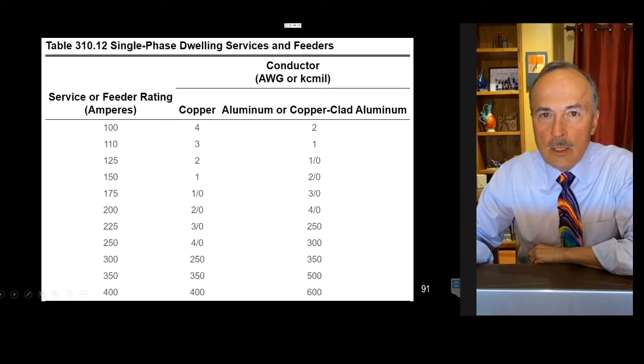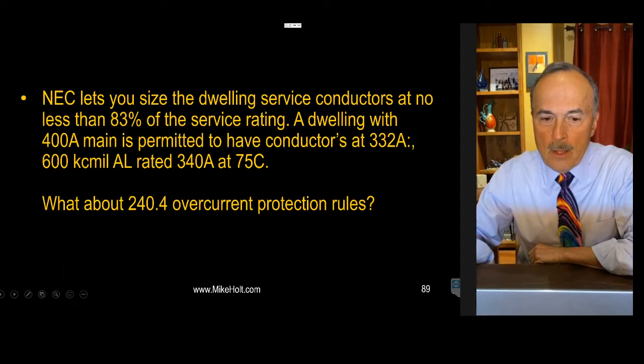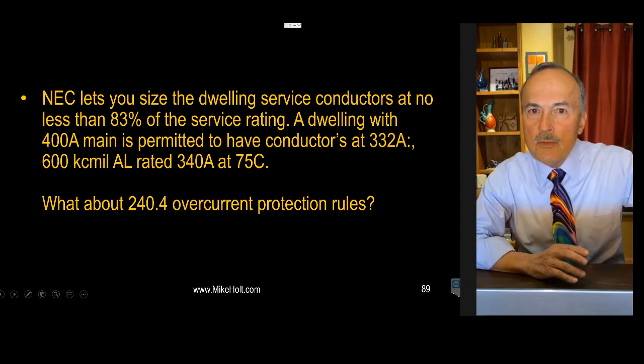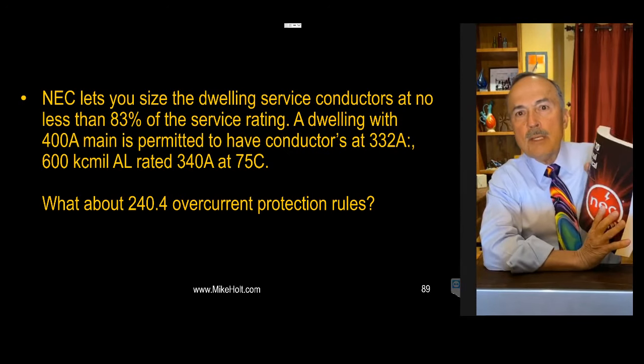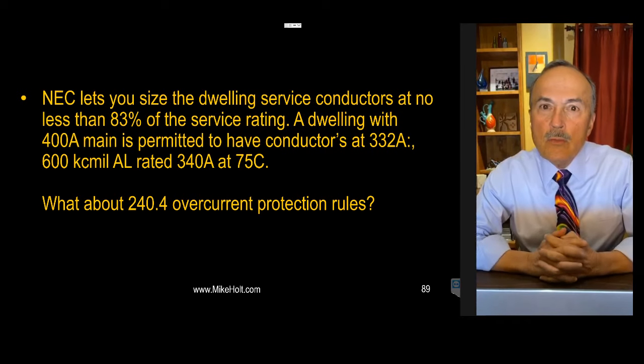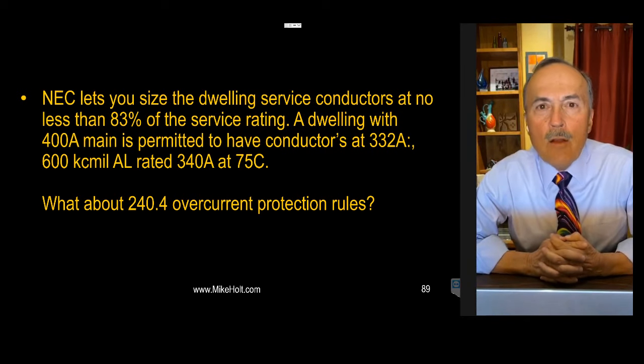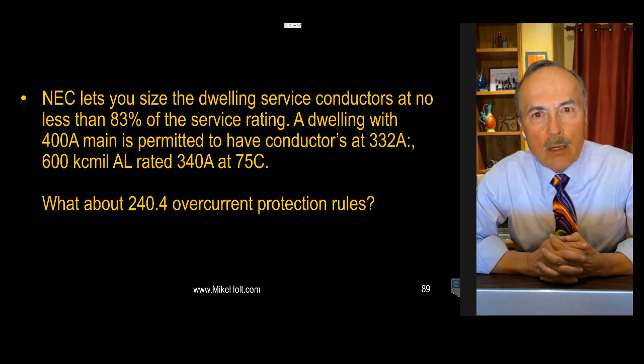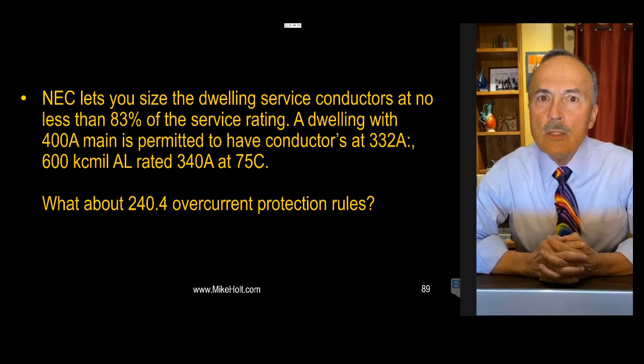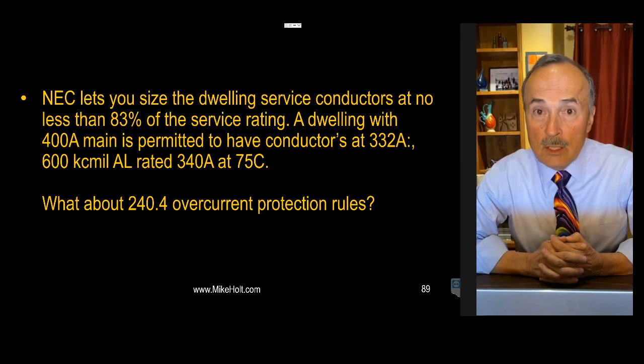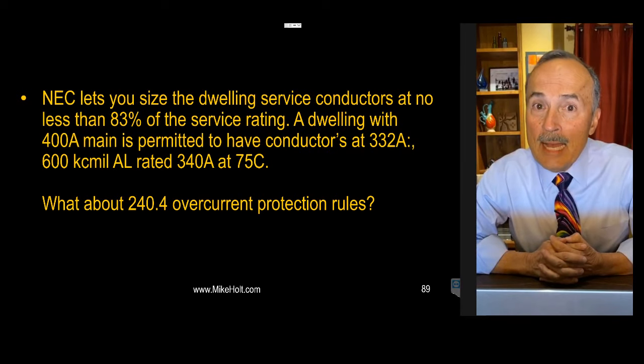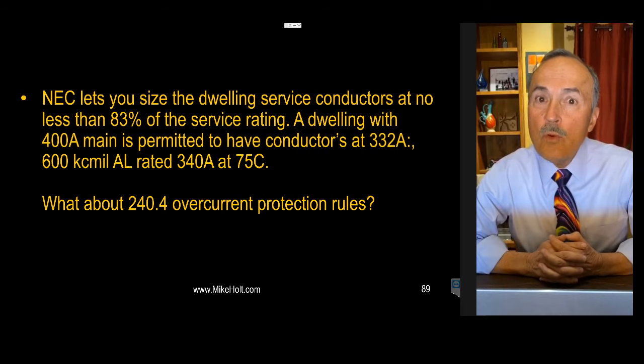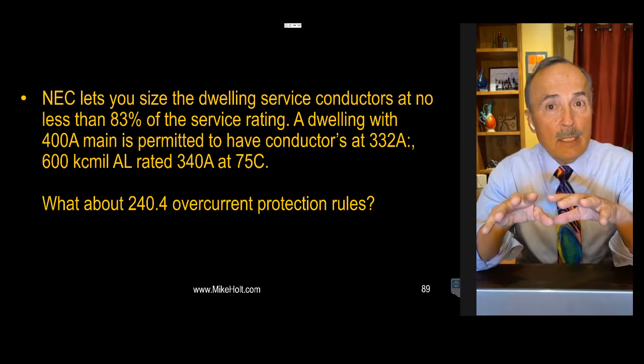I submitted a public input, saying, can we forget about the 83% and allow us to put the table back the way it was? So in the 2020 code, it brought it back. But in that process, I started thinking, wait a minute. Look at that 400 amp service. You could use 600 kcmil aluminum. What's the ampacity in Table 310.16 of 600 kcmil aluminum? It's 340 amps. How can you put a 400 amp breaker on 340 amp wire? There's no rule that allows that.